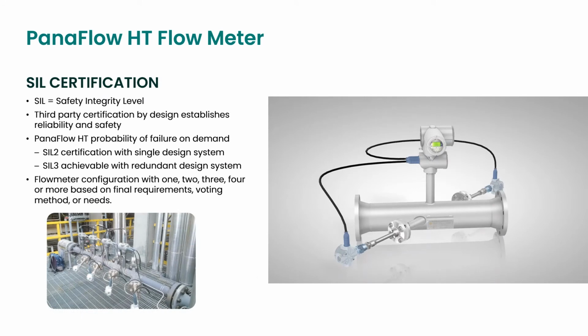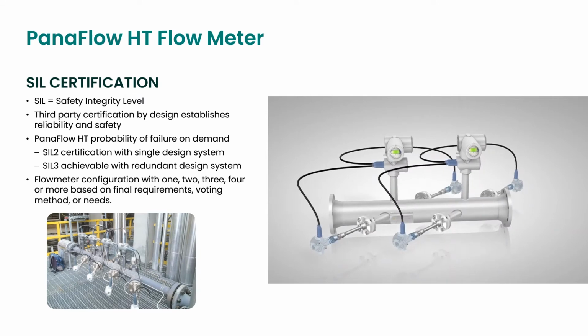PanaFlow HT is used for both process and safety control systems. With SIL certification, we achieve this certification by design. With the PanaFlow HT, we achieve a SIL 2 certification level with a single system and SIL 3 with a redundant design system as shown on the right. However, with the PanaFlow HT system, we have multiple configurations of 1, 2, 3, 4, or more based on the SIL requirements and voting system at the measurement point. Here's a picture of a 4-path system on the bottom in which 1 point of measurement goes to the process control system and 3 measurements are going back to the safety system.